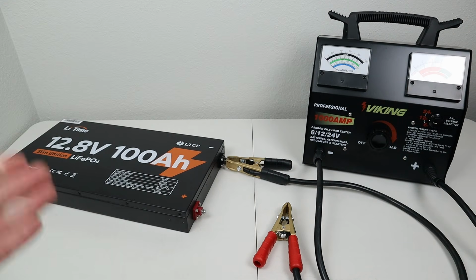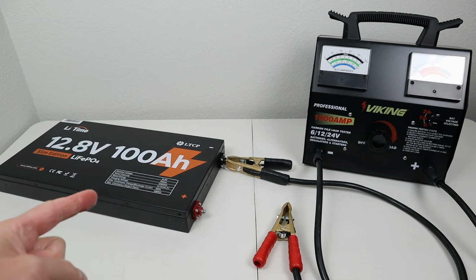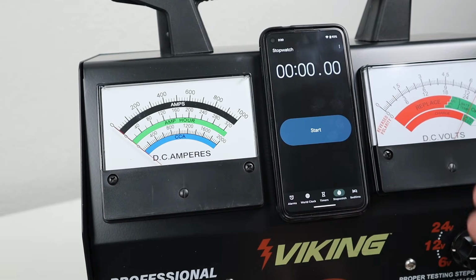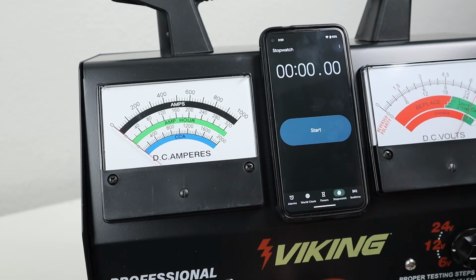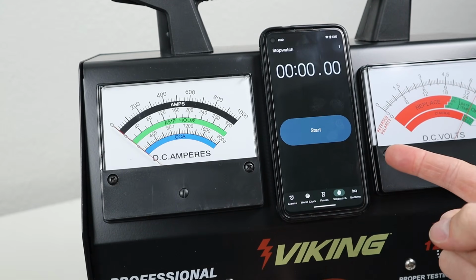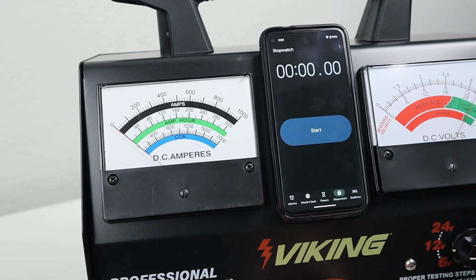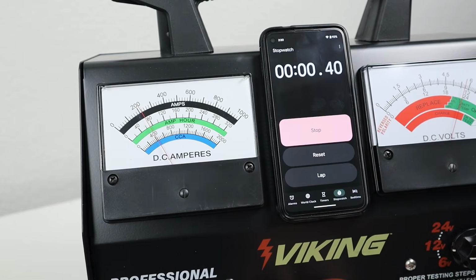Essentially, we can just turn up the amps to see when the BMS will shut off the load. For the first test, I'm going to pull 200 amps continuously just to see if the BMS will shut off. I'll start the load, then start the stopwatch, and we'll see how long it goes. Let's get it up to 200 amps, then we'll start this.